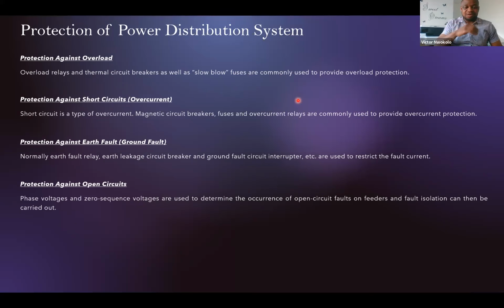So with overload, say your current setting for a breaker is 6 amps. If for any reason, due to demand on the other end or improper design, the load side is pulling maybe 6.5 amps, the protection device will see that as an increase over the 6 amps it is rated for, and we continue to monitor this for a period.